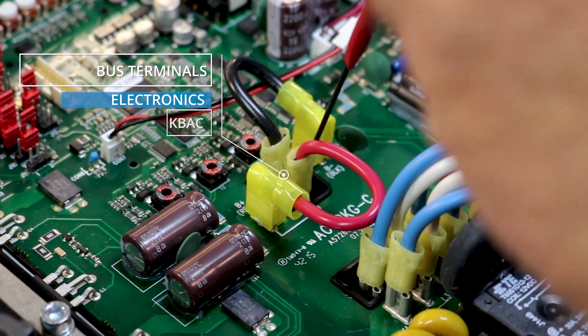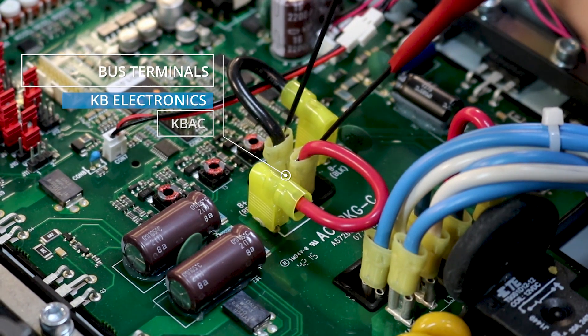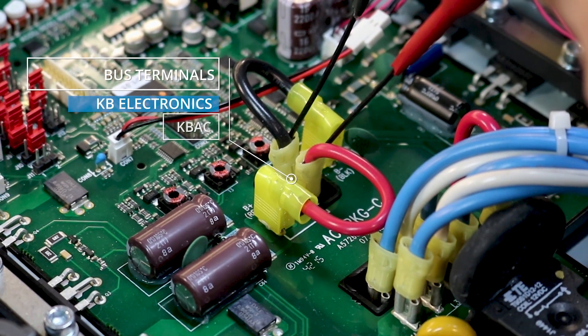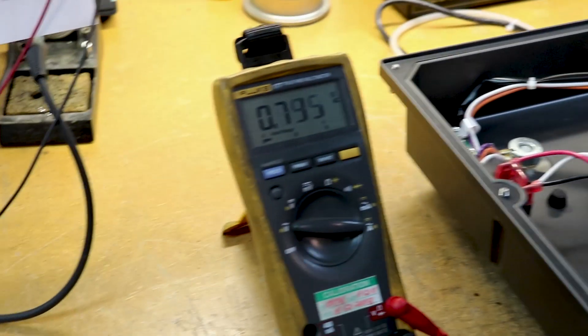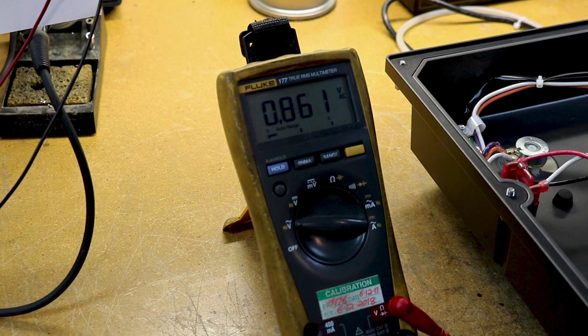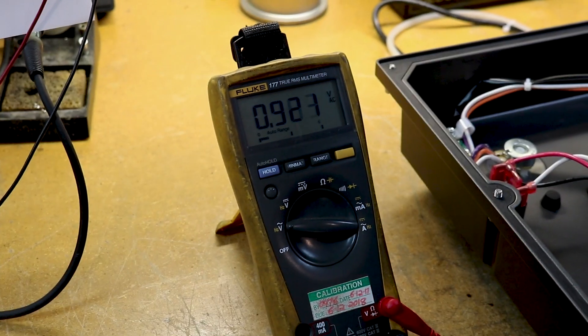With a light load on the drive, aim for under 20% of the rated output current. You should measure less than 1V AC RMS if your drive's bus capacitors are in good shape.